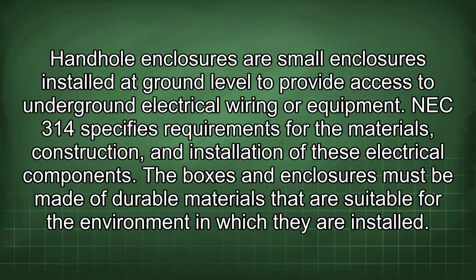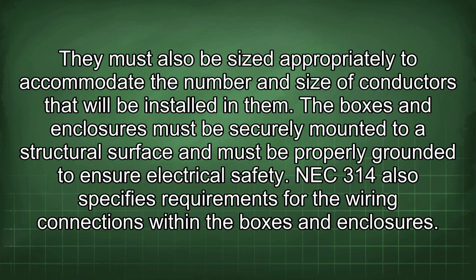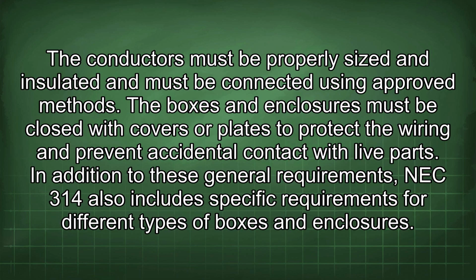The boxes and enclosures must be made of durable materials that are suitable for the environment in which they are installed. They must also be sized appropriately to accommodate the number and size of conductors that will be installed in them. The boxes and enclosures must be securely mounted to a structural surface and must be properly grounded to ensure electrical safety. NEC 314 also specifies requirements for the wiring connections within the boxes and enclosures. The conductors must be properly sized and insulated and must be connected using approved methods. The boxes and enclosures must be closed with covers or plates to protect the wiring and prevent accidental contact with live parts.